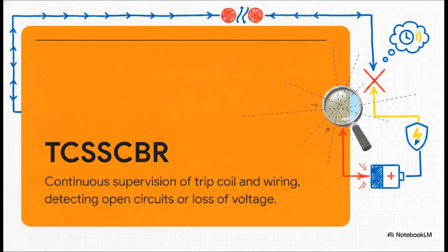So here's exactly what this function does. TCSSCBR provides continuous supervision of the trip coil and its associated wiring. It's looking for open circuits or loss of control voltage. And it does this by quietly running this tiny, totally harmless test signal, we're talking about 1.5 milliamps, through the trip circuit at all times. It's just a proactive, constant physical ping. If that 1.5 milliamp current ever stops flowing, the relay knows instantly, hey, the path is broken.